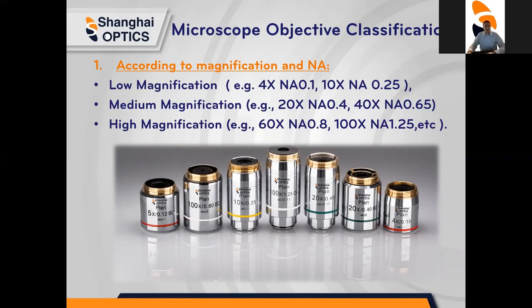Magnification helps to enlarge the image and numerical aperture helps to distinguish the details in the image. So when you see 4x or 60x, that is the amount of power the objective contains to increase the visibility of the object. An NA of 0.1 would indicate an objective that doesn't have as much ability to show the details of the object versus an objective with NA of 1.25. The image will not only appear with greater resolution but with better quality as well.